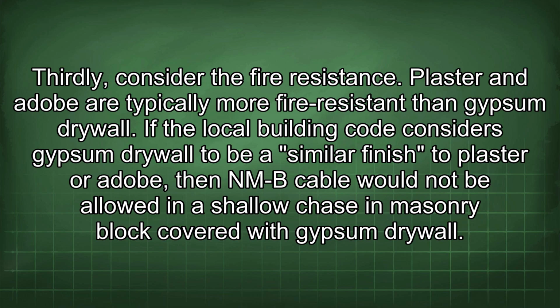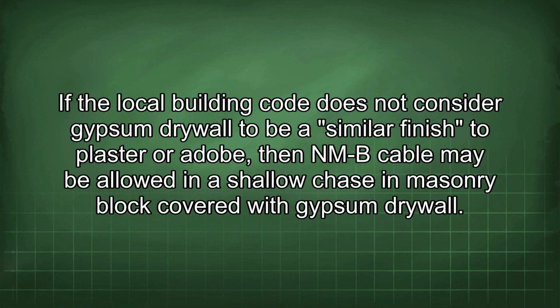Thirdly, consider the fire resistance. Plaster and adobe are typically more fire resistant than gypsum drywall. If the local building code considers gypsum drywall to be a similar finish to plaster or adobe, then NMB cable would not be allowed in a shallow chase in masonry block covered with gypsum drywall. If the local building code does not consider gypsum drywall to be a similar finish to plaster or adobe, then NMB cable may be allowed in a shallow chase in masonry block covered with gypsum drywall.